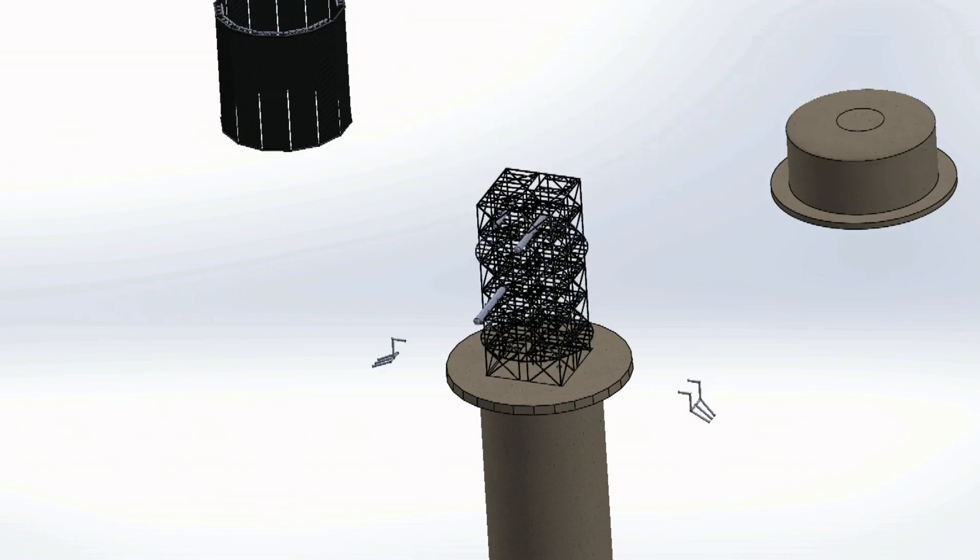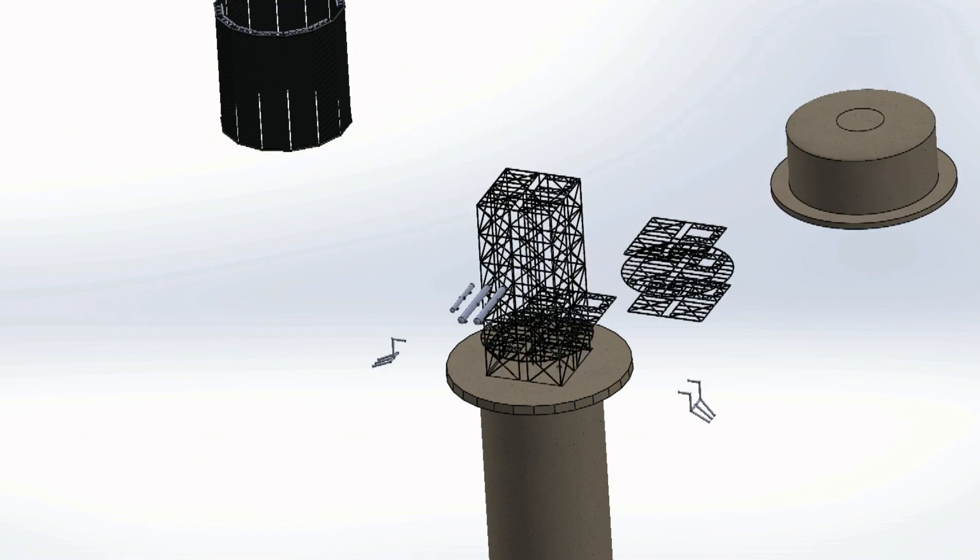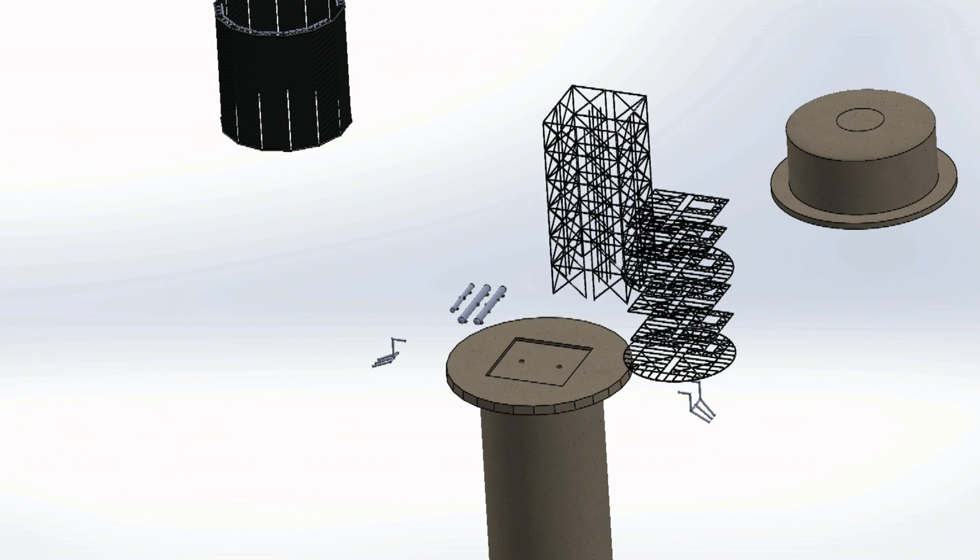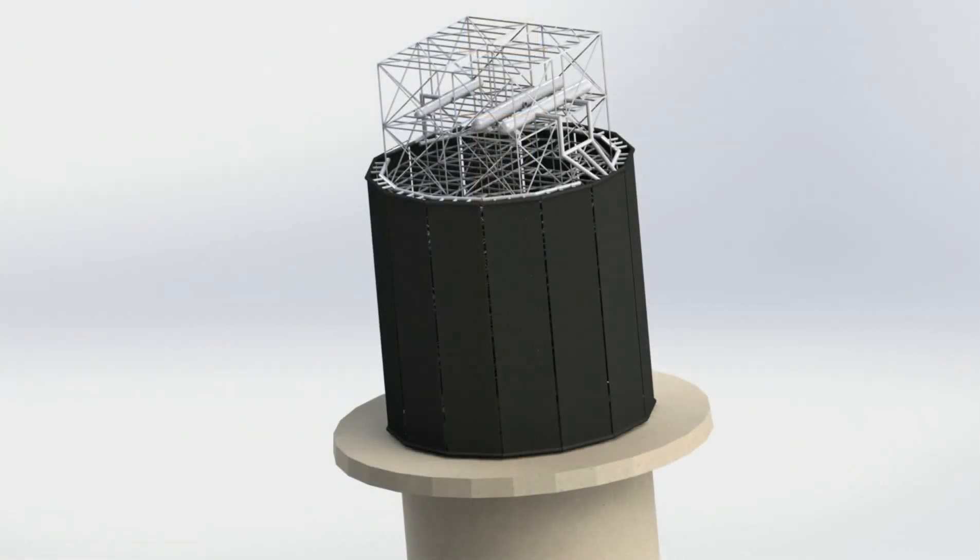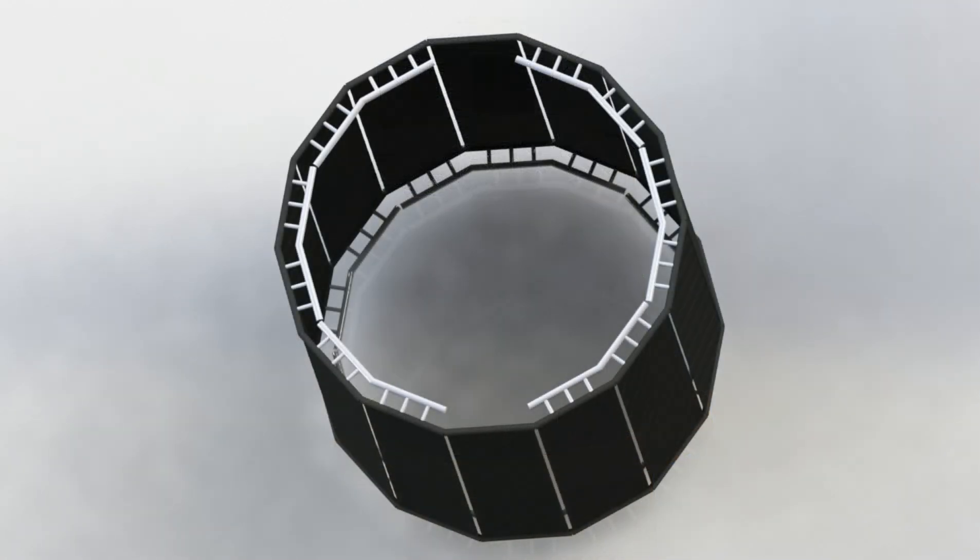The top of the tower contains the solar receiver where sunlight interfaces with the sodium and potassium nitrate mixture, increasing the mixture's temperature from 220 degrees to 550 degrees Celsius. The mixture flows into two inlet tanks and through 14 tube panels, each containing 65 adjacent tubes. The outlet tank sends the heated mixture down to the hot salt tank for storage.